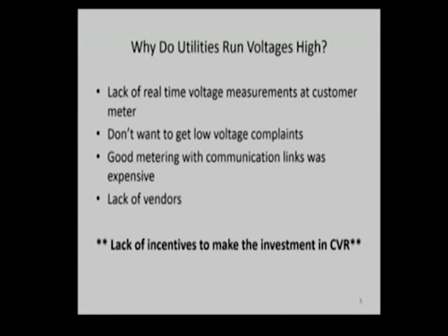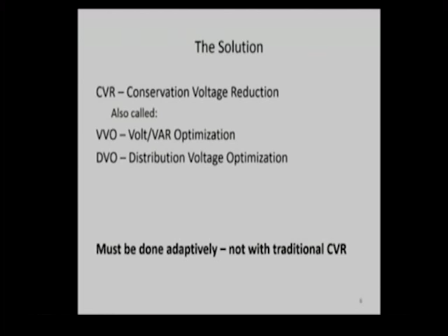The solution I'll talk about this morning is called conservation voltage reduction, also called volt-VAR optimization or distribution voltage optimization in other states. This isn't a new technology, but it's new in how it's being piloted around the country now. It must really be done adaptively, meaning you need meters out in the grid, and you need to do it on an ongoing basis, because you can't just set the voltages at one level and let it go, or you'll get into problems.